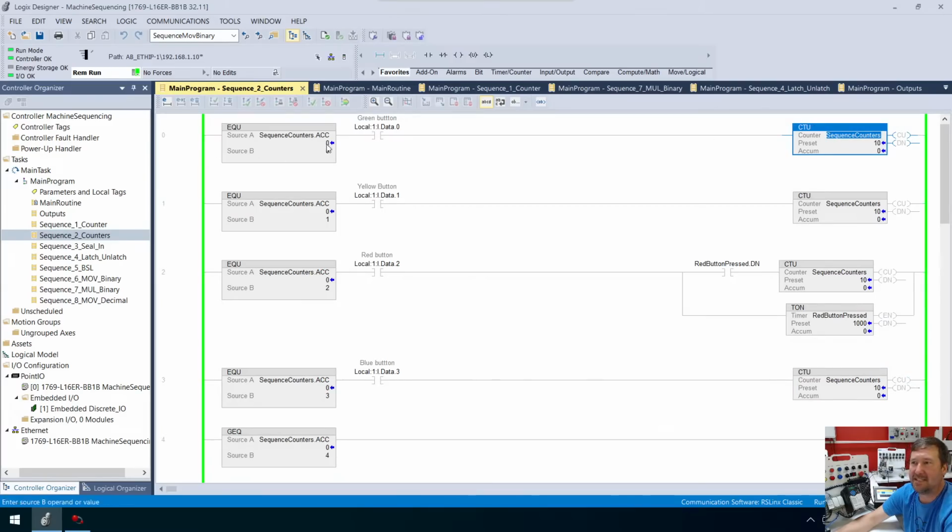I think this makes it easier to read if you're troubleshooting. Because for sequence step 0, 1, 2, and most importantly, I can combine the timer nicely so that when I'm on step 2 and trying to figure out what is wrong, it's going to be really clear that it's either waiting on this or waiting on this. I'm not going to have to scroll or search to go find it.